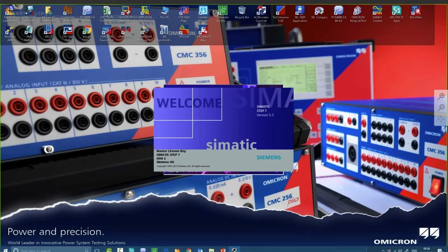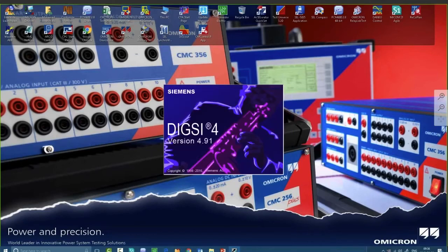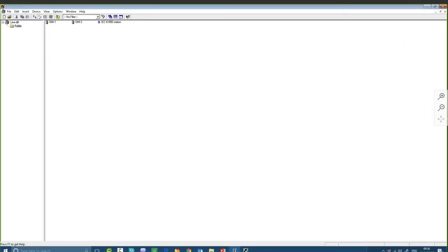First of all, I have a big warning when using the PTL. We have one important recommendation: don't use online retrieving of settings. Why? Because maybe somebody changed the settings. At that time, what will happen? You will import the wrong settings into your file, and you will compare the wrong settings to the wrong testing file. Then you will get a success answer that it passed, but this is not correct.